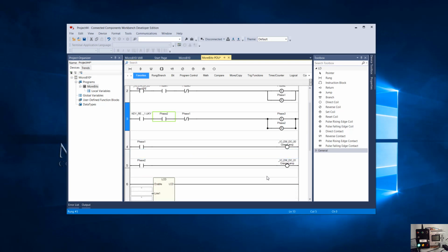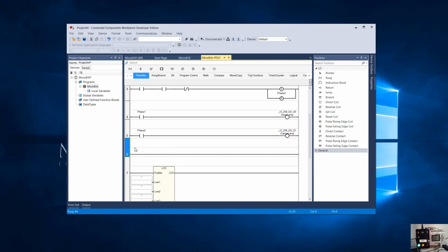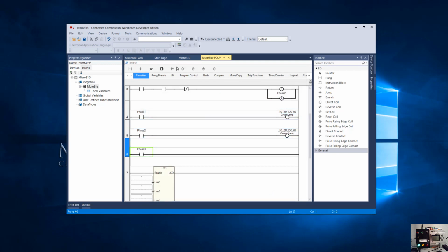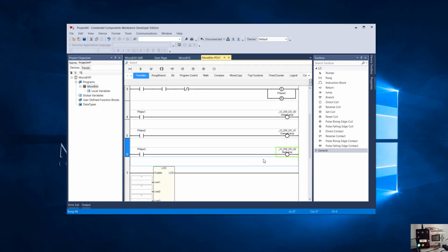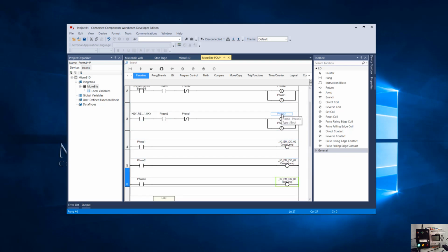Okay, and then to get for phase 3, let us say we want, oops, I didn't want to put it there. I want to move it down so they're in order. Okay, and then we'll use our phase 3 bit again to control, let's see, we got the red lamp left. Okay, and one thing to note here is I am not using set or reset on these green and orange and red lamps. I'm using the direct contacts, and I'm controlling them using the bits, which are being set and reset. Does that make sense? So they're staying on even after I hit the push button because the phase bit is being latched or sealed in, if you want to say it that way.